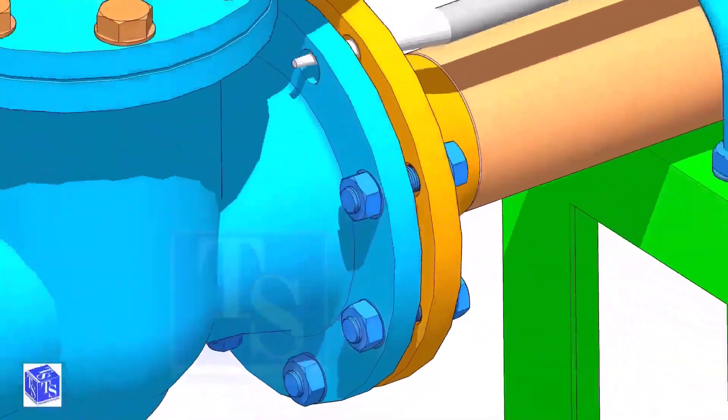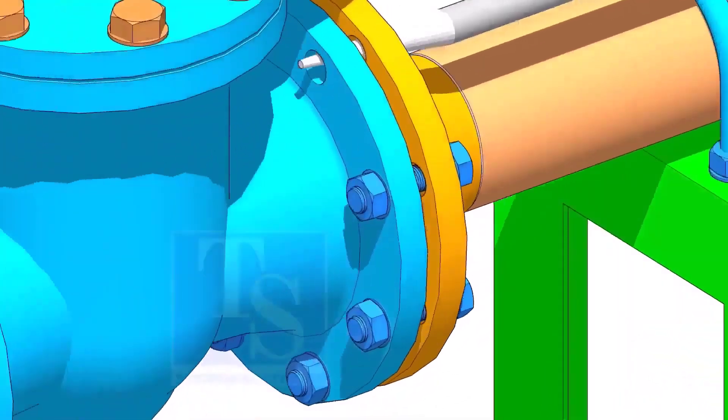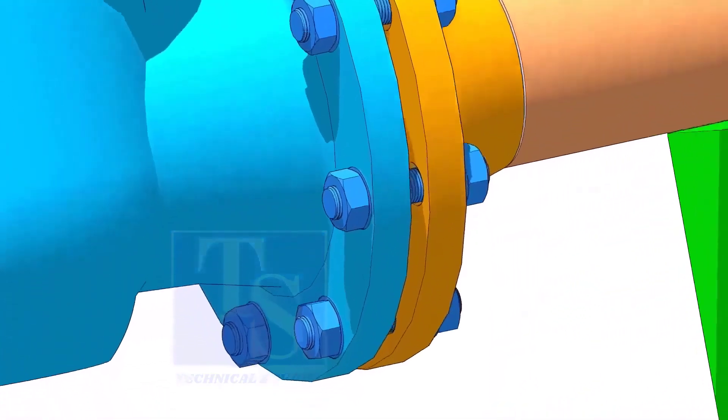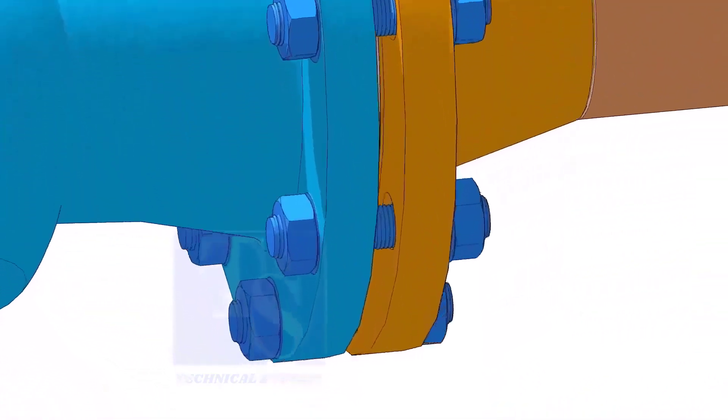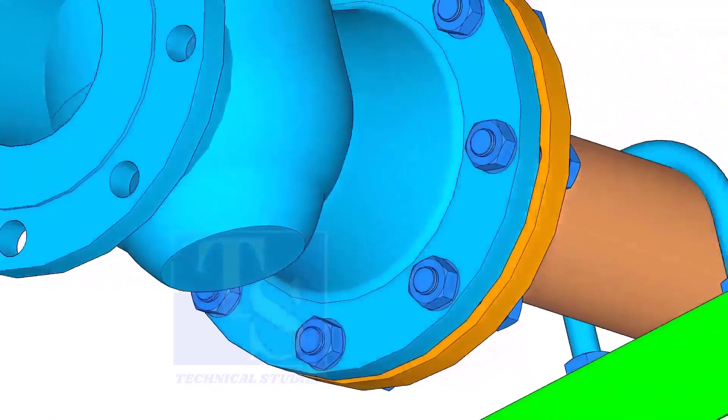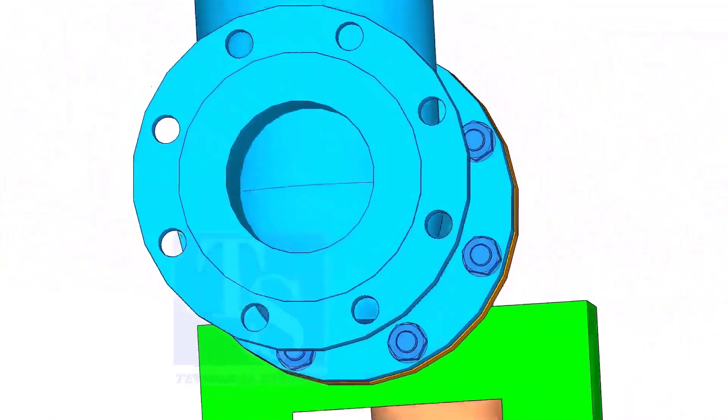If the flange overlap, the gasket position, etc., is in the acceptable limit, hand-tight the bolt. Use an aligning bar for this. After slightly tightening the bolts, put the last bolt.